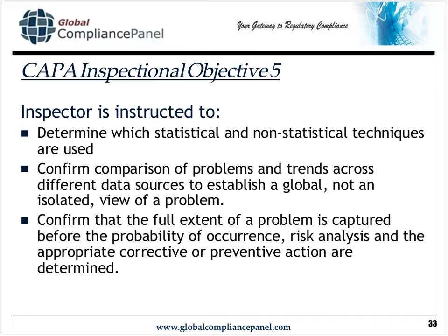If I'm able to capture all of these types of rejections in process, but they never hit the field, that shows I'm doing a good job of capturing that data, and my acceptance criteria and test procedure are good. However, as my in-process rejects rise, so do my complaints in the field for the same characteristic, I'm not doing sufficient corrective action or investigation.